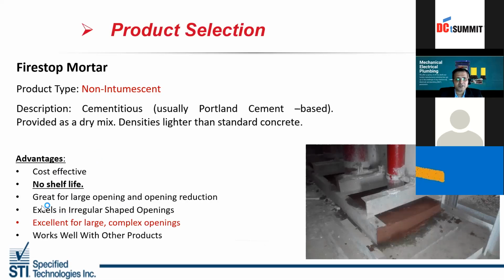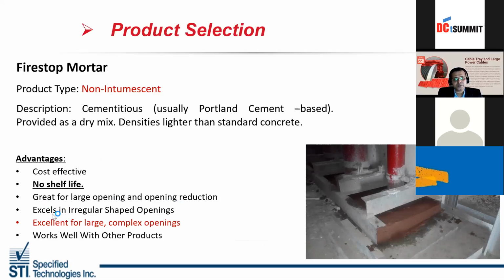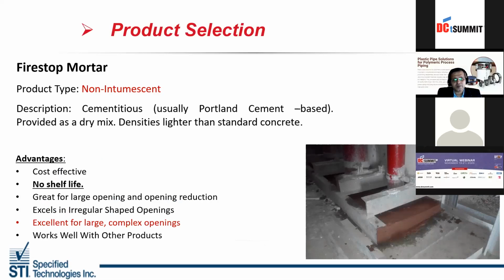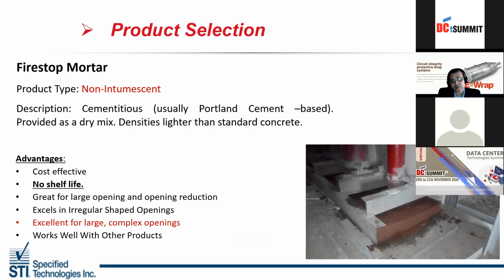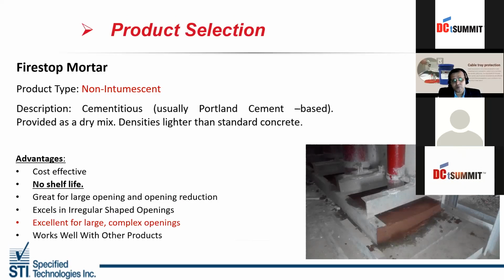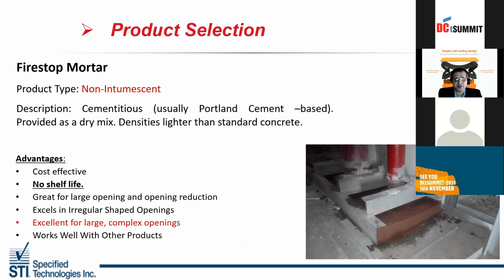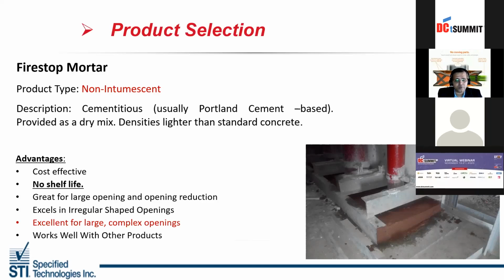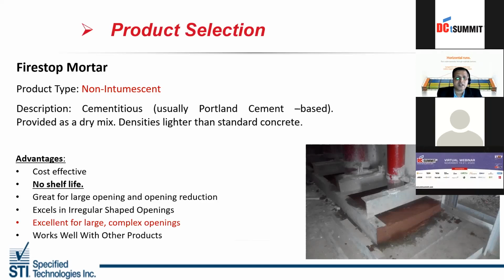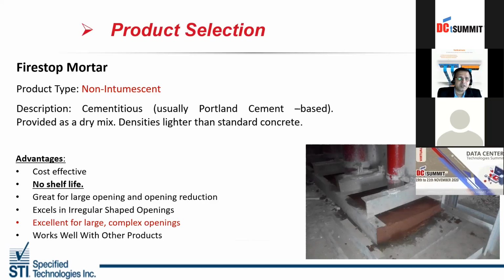Now, as I mentioned, it is used for a larger opening, and it is used for irregular openings also, because this is a Portland cement. It can be used as a dry mix, and if you increase the water, it will be free flow. So it will go into all the corners wherever ducts and metallic pipes are there. It will close the gaps between those and the wall or floor. Third, this doesn't add weight to the building. It's a lightweight Portland cement.